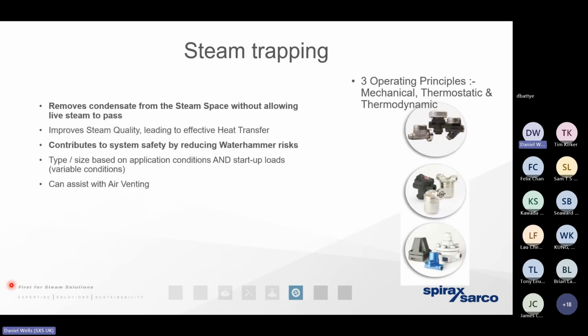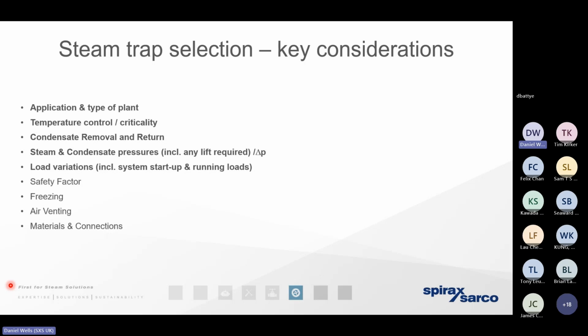So we mentioned steam trapping when we met 2 weeks ago. The steam trap really is that interface, the barrier between the steam, the gas, the useful heat energy. And downstream of the steam trap, we've got the condensate, the liquid, the byproduct, far less heat energy, but still high temperature hot water. I'm not going to labour the point of the importance of steam trap selection and also steam trap sizing. If the steam trap fails in the open position, sooner or later we're going to find that the steam and also that condensate is lost to the atmosphere. If it's in the closed position, the condensate can't get away, it's going to back up, and it's either going to flood the heat exchanger, which we're going to know about reasonably quickly, or it's going to back up and flood the infrastructure. And that's when the effects are going to creep up on us slowly over time. So steam trapping is vitally important.